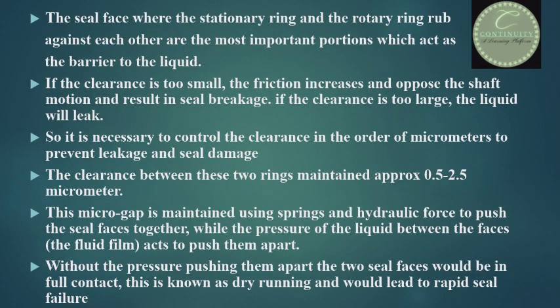The surfaces where the stationary ring and the rotary ring rub against each other are known as seal faces. These are the most important portions, acting as the barrier to the liquid. If the clearance is too small, friction increases and opposes shaft motion, resulting in seal breakage. If the clearance is too large, liquid will leak. The clearance is maintained at approximately 0.5 to 2.5 micrometers.